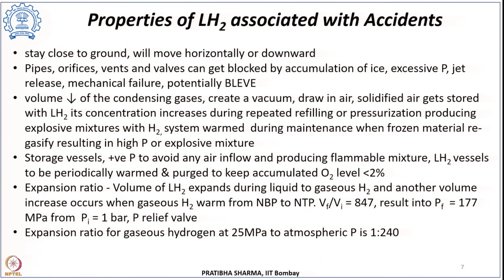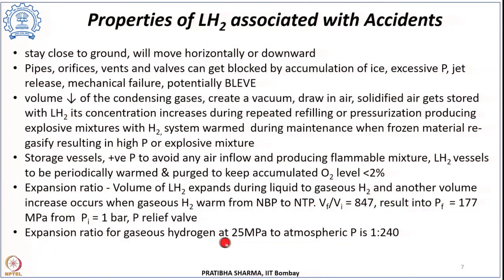This massive pressure increase means a pressure relief valve is an integral part of liquid hydrogen storage facilities. Similarly, for compressed gaseous hydrogen stored at 25 MPa, if there is a leak to atmospheric pressure, the expansion ratio is 1:240.